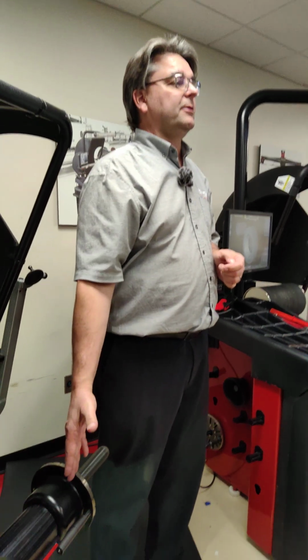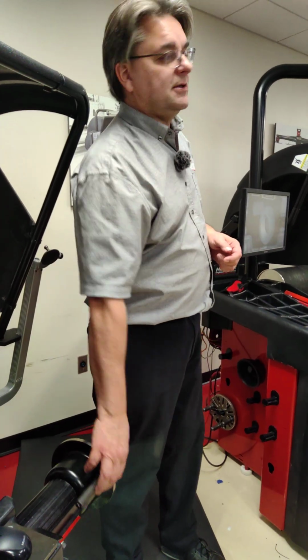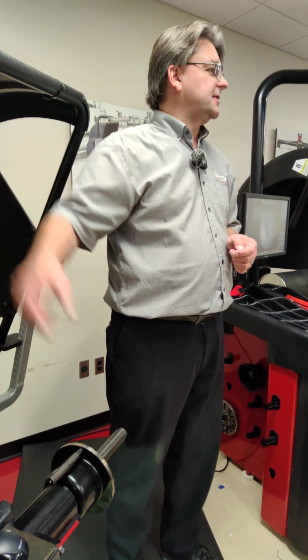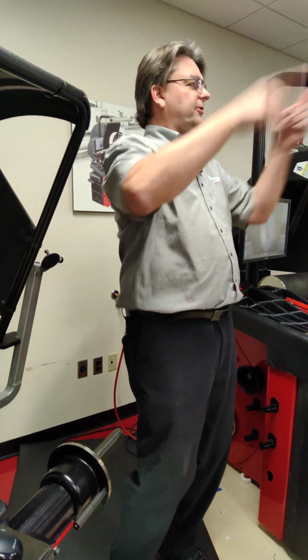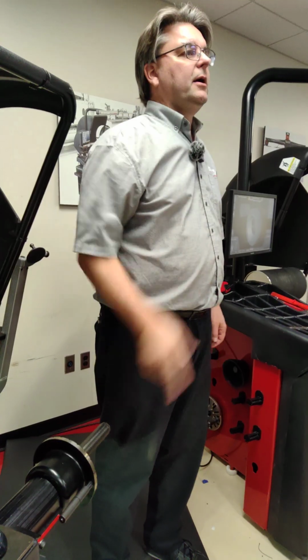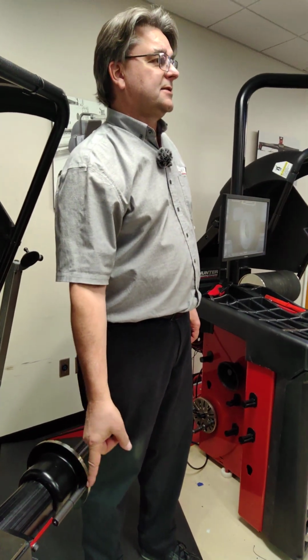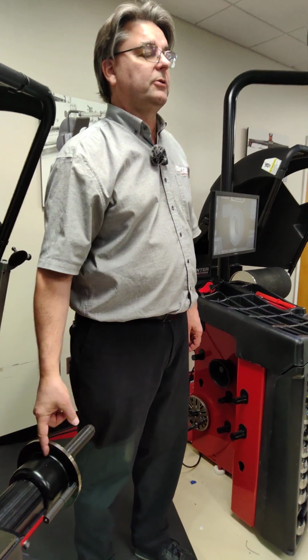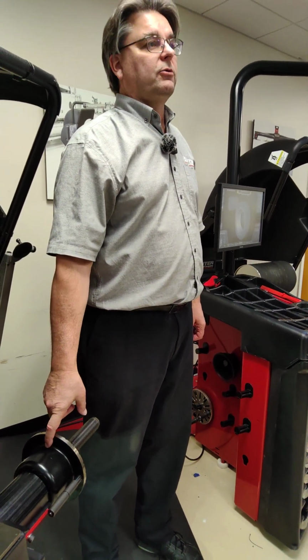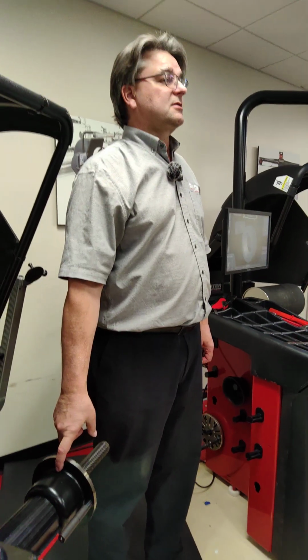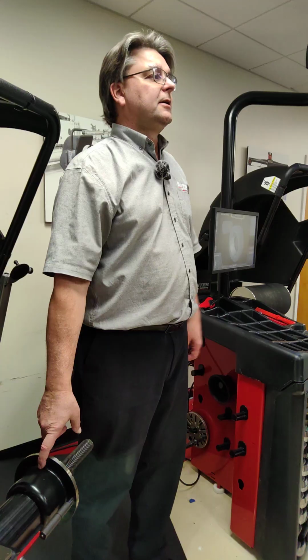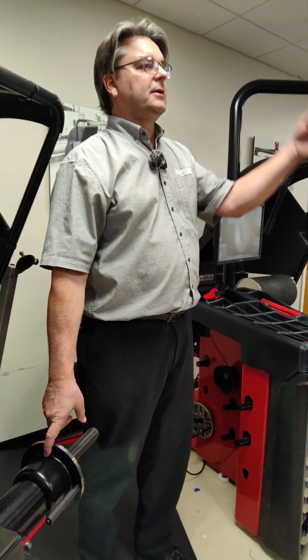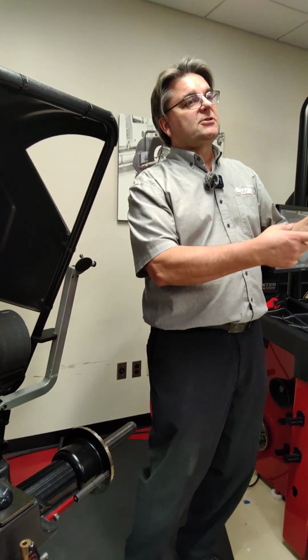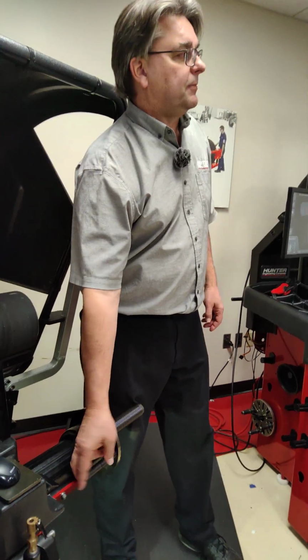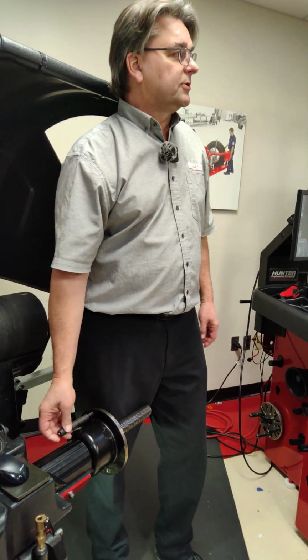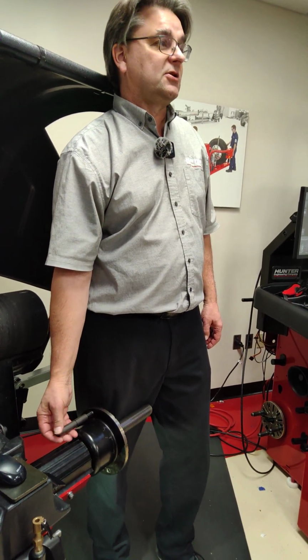Like when they calibrated the balancer themselves, they didn't realize that you actually moved this up to 12 o'clock before you hit OK on step 2. They put the weight on and they just see you fiddle farting and they go, oh, if I just hit OK, I can make it go. And then it thinks that it's 12 o'clock. So it's expecting the weight to be here, but you're putting the weight here, which means the weight you put on is not where it wanted it to. So then you spin it again, and it asks for more weight in a different spot, and then it spins it again, just like this. And you keep spinning it, and you keep putting on weight, and it keeps asking for more weight in a different spot because it's chasing weights. Again, 90% of the time, the balancer is just doing what it was told, but it was told to do something silly. So the end result is it's chasing weights.